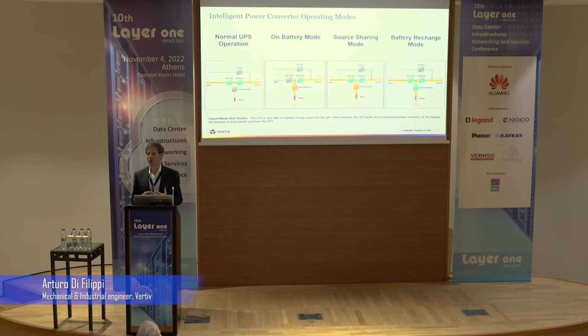You know how the normal operation of the UPS is working, so nothing to discuss there. It's double conversion. You can also have some other operating modes, but anyway, you get to the load. Okay, this is a very simplified image, but you need to account for some efficiency, but you get 800 kilowatt input, 800 output, nothing else. Then if you have the firmware to support the grid service operations, you could just decide to disconnect from the grid from time to time. And for instance, as we were saying before, you disconnect from the grid where there is under frequency, or just you want to during the day. And in that case, in the battery mode, you get all the load from the battery.